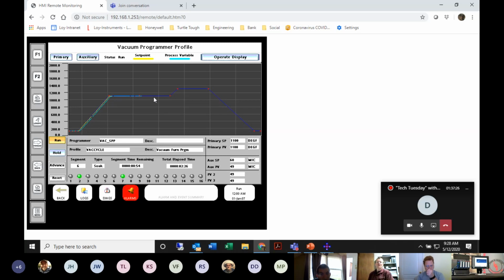But what this does is allow the operator to not only see the set point and process variable tracking along this blue line, but also to make sure that the set point profile is the profile they want to run before they hit the run button. And it gives them a nice, complete picture of that profile to allow them to sign off on it and proceed with the process.